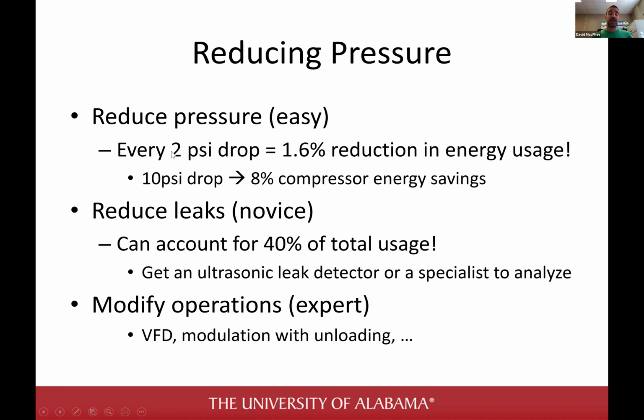A rule of thumb that we've verified many times using more sophisticated means is that if you can reduce 2 psi in around the 100 psi range, you're going to realize a 1.6 reduction in energy usage. So we recommend every plant that we go to, unless they have a process that requires a certain compressed air pressure, just do a 10 psi drop. Then you get an 8% compressor energy savings. That ends up adding up quite a lot, and it's very easy to do.